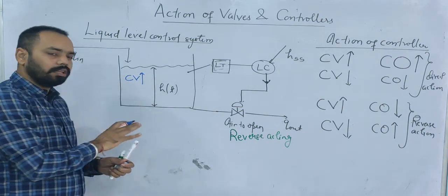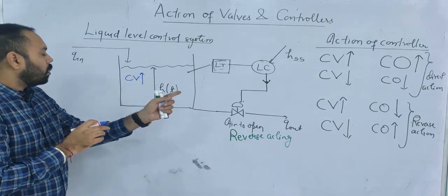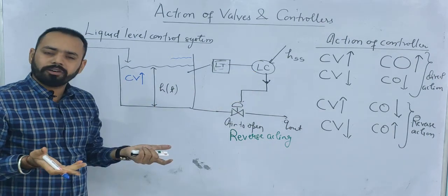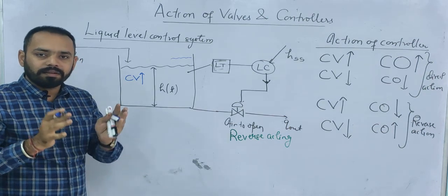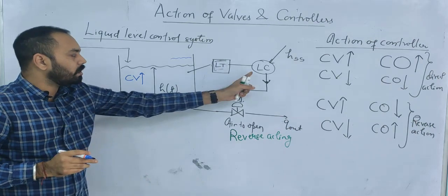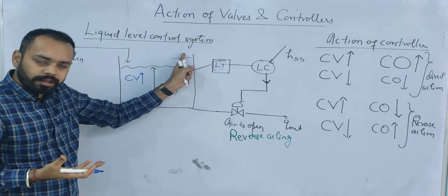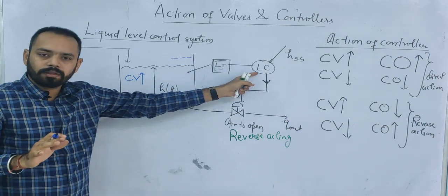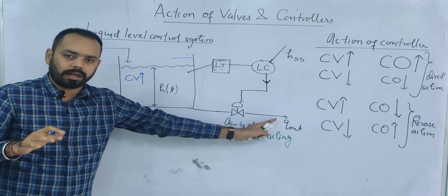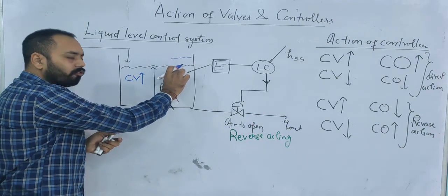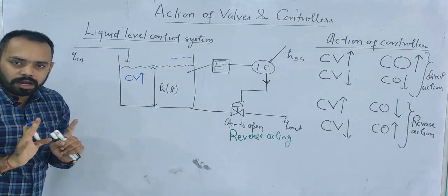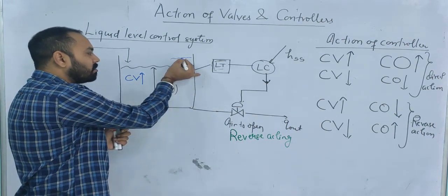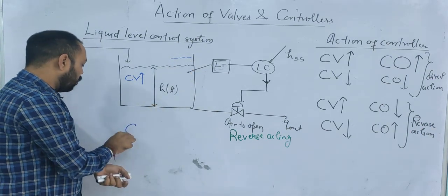If the liquid level has increased, what should the controller decide? The controller is the brain of the control system — it must restore the liquid level to its set point. To decrease the level, the controller should increase the outflow by opening the outlet valve. The inlet flow rate is a disturbance and is not under control; the manipulated variable — the outlet valve — is under the controller's control. So: CV has increased, and the controller needs to direct the valve to open.